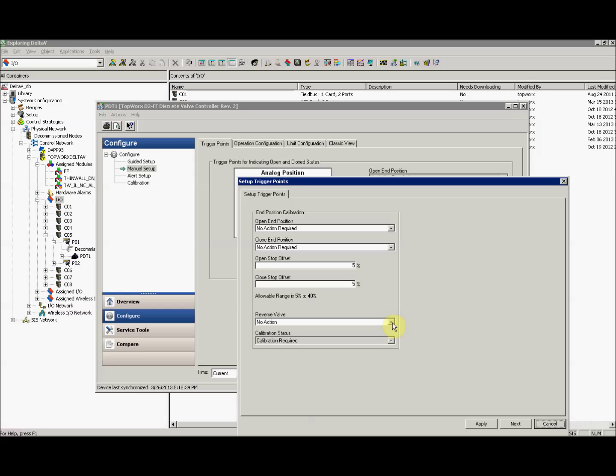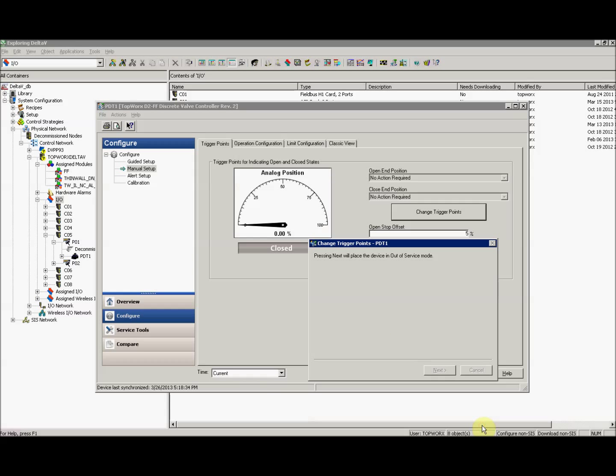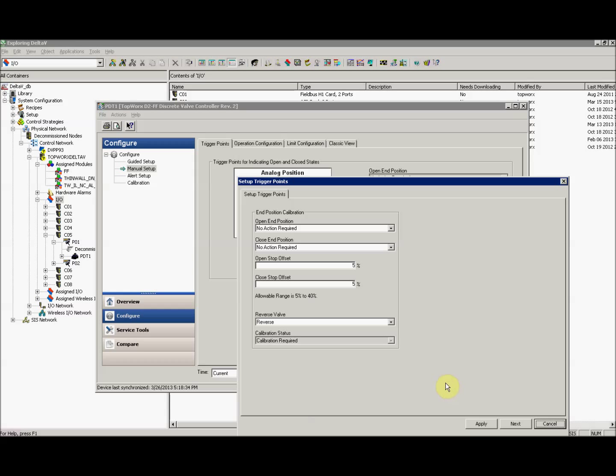Now towards the bottom, you will see a window labeled Reverse Valve. Select Reverse and hit Apply. And it should reverse your valve. If it's closed, it'll move to open, and if it's open it'll move to close. And this is how you can stroke between open and close via AMS.